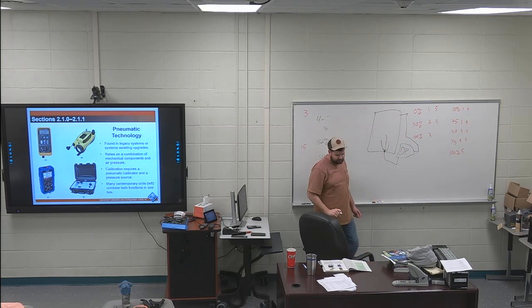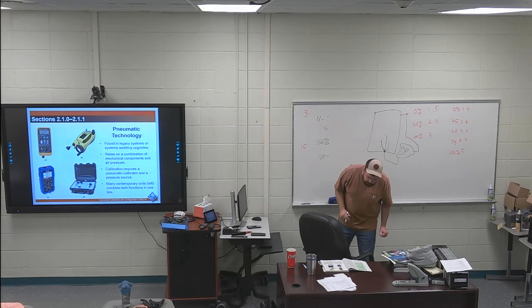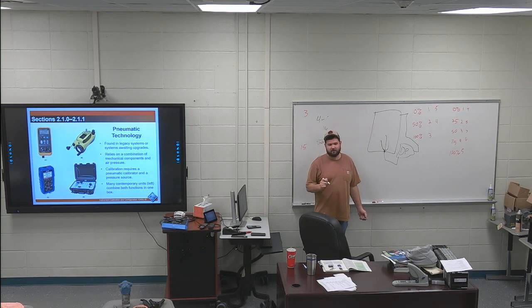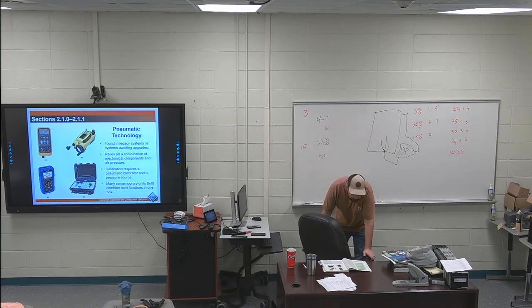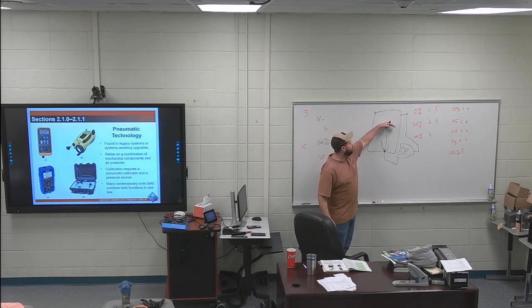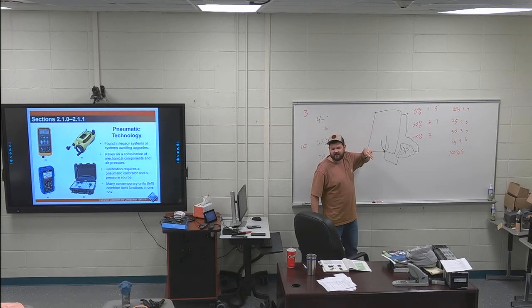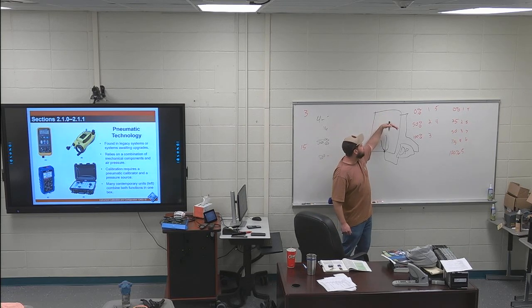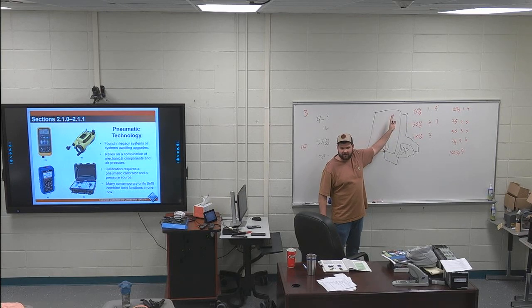And they have wet leg on there too. So I have wet leg and dry leg. My dry leg would be if whatever's in this tank doesn't condensate or slosh around, if whatever's in this tank doesn't get in this pipe, then I can leave it dry.